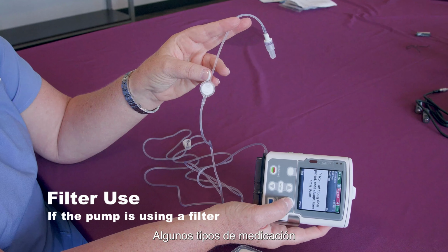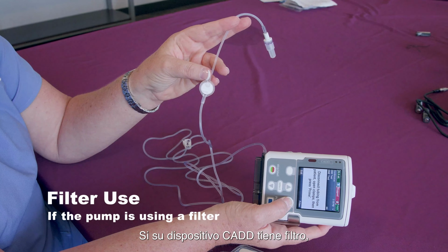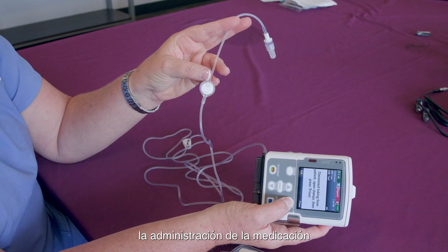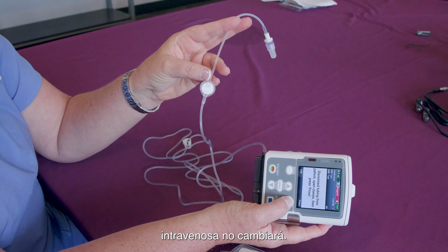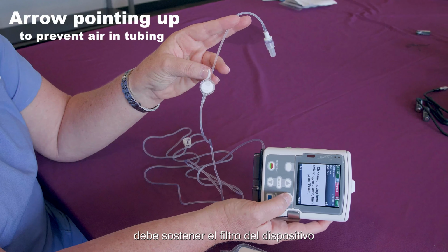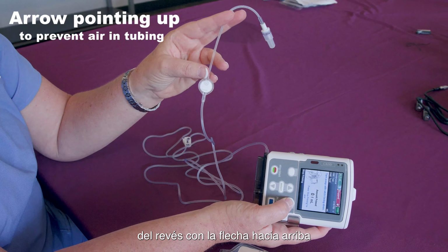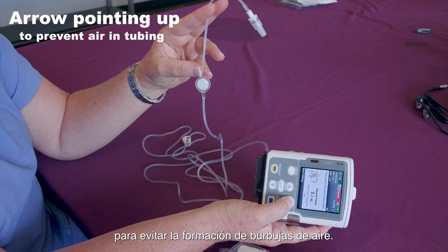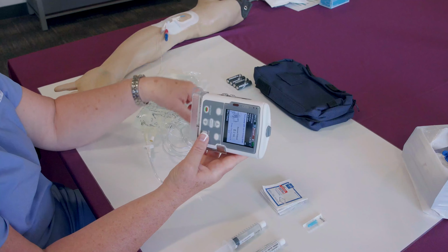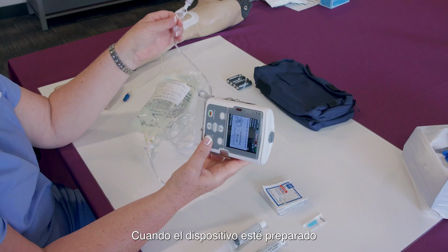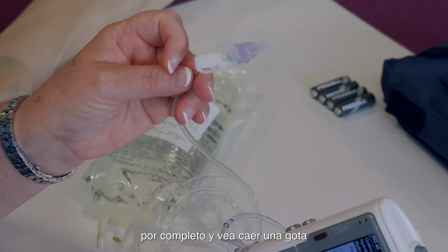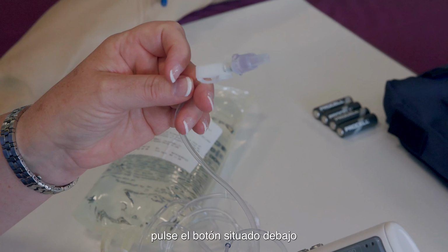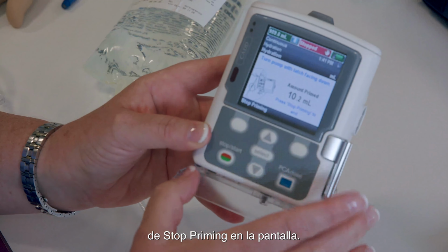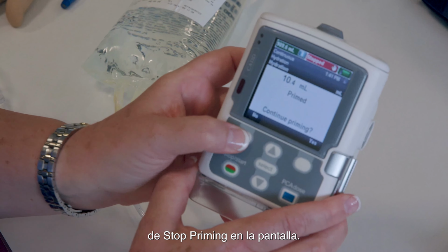Some medication will require filtered tubing. If there is a filter on your CADD tubing, it will not change how you administer your IV medication. However, during priming, the tubing filter is to be held upside down with the arrow pointing up to prevent air bubbles in your tubing. When the tubing is fully primed, and you see a drop of liquid in the cap at the end of the tubing, press the soft button under Stop Priming on the screen.